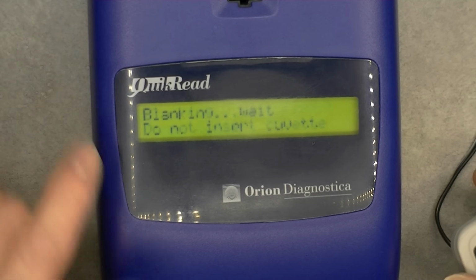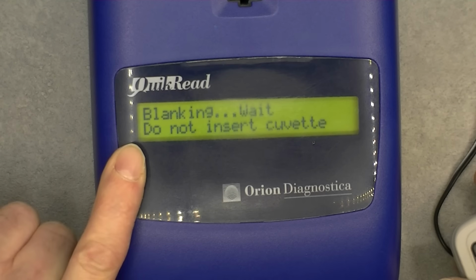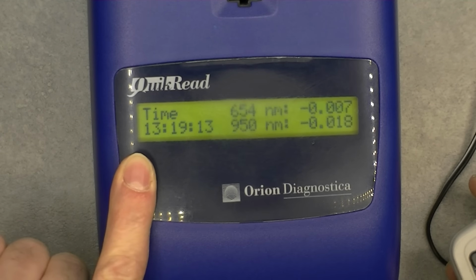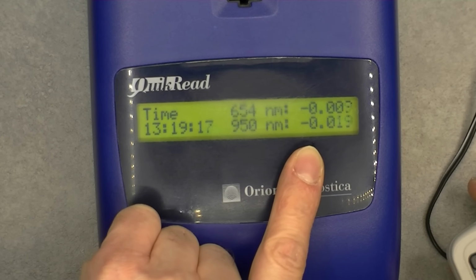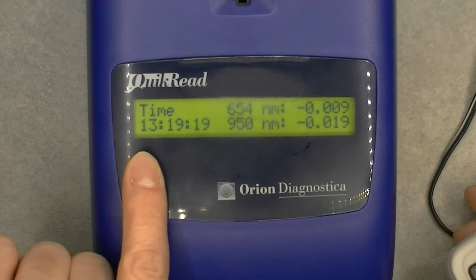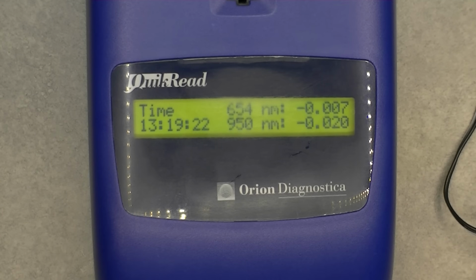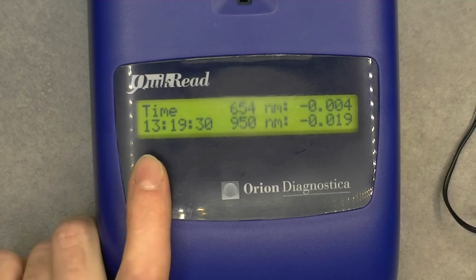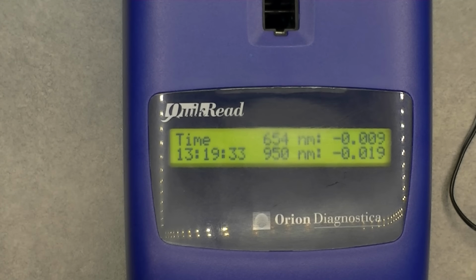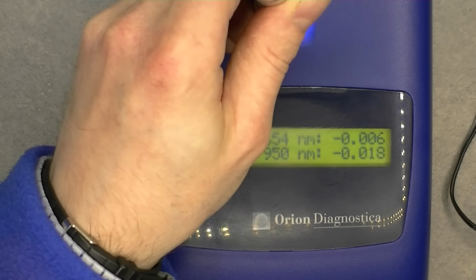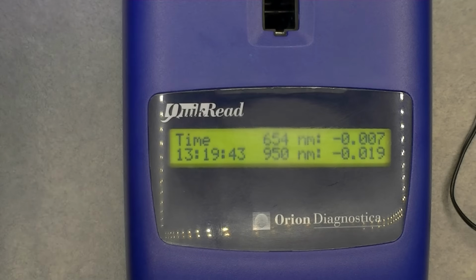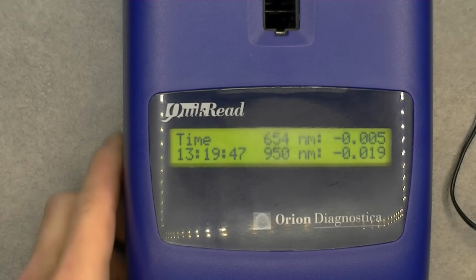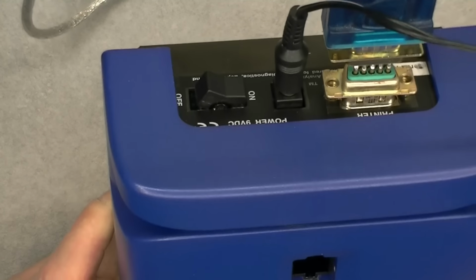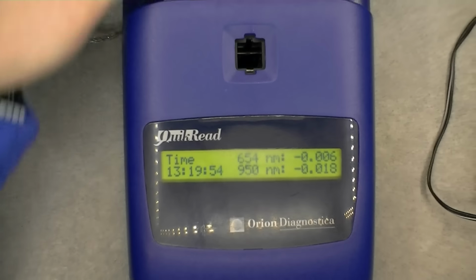So same logo on screen, and you have blanking, do not insert cuvette, and it gives you this information, 2 wavelengths with 2 power levels maybe, and the time, which is off by 1 hour, but which is accurate. So, as it did come from Austria, maybe it is normal you have 1 hour of difference. So what happens if I shine a light inside? You can see, yes, we are changing the measurement. So interesting. There is not much else to see. So I will turn it off.